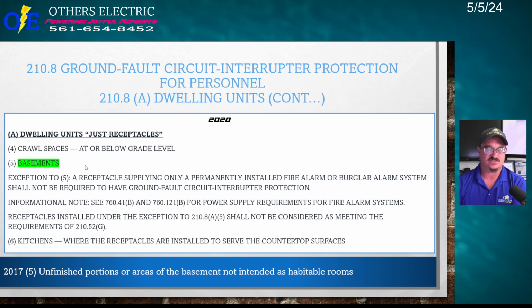Here are the exceptions to this. These circuits don't have to be GFI protected. Receptacles supplying only a permanently installed fire alarm or burglar alarm system shall not be required to have ground fault circuit interruption protection. So if you've got a 120 volt receptacle for a fire alarm panel or a burglar alarm panel in your garage, it doesn't have to be GFI protected. And if it's in the basement, exception to 5, receptacles supplying only a permanently installed fire alarm, it doesn't have to be GFI protected either.